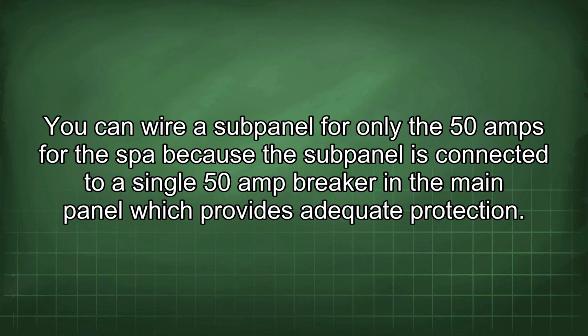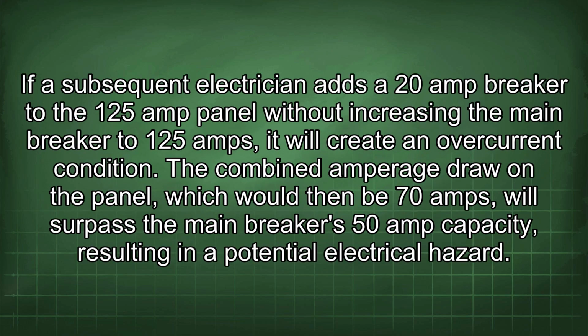You can wire a subpanel for only the 50 amps for the spa because the subpanel is connected to a single 50 amp breaker in the main panel, which provides adequate protection. If a subsequent electrician adds a 20 amp breaker to the 125 amp panel without increasing the main breaker to 125 amps, it will create an overcurrent condition. The combined amperage draw on the panel, which would then be 70 amps, will surpass the main breaker's 50 amp capacity, resulting in a potential electrical hazard.